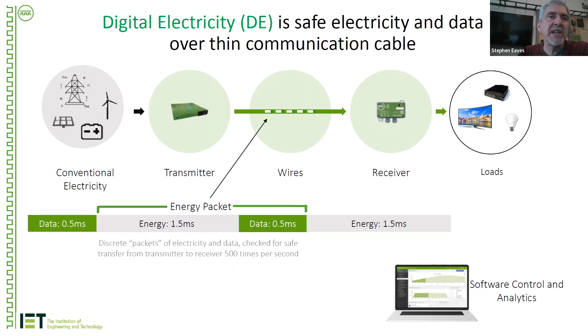On the bottom of the screen here, you're looking at the general format that we use for transmission. It's a small burst of electrical energy, a pulse of electrical current, and then a period of what we call the data component, which is only 500 microseconds in duration. During that data period, that's where we're verifying, using digital signal processing, that the energy component made it correctly to the other side.